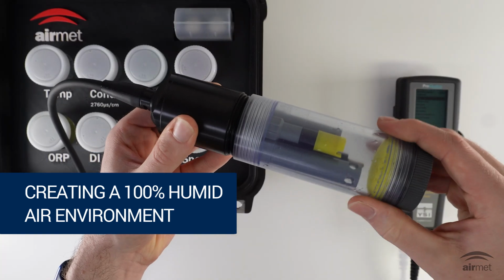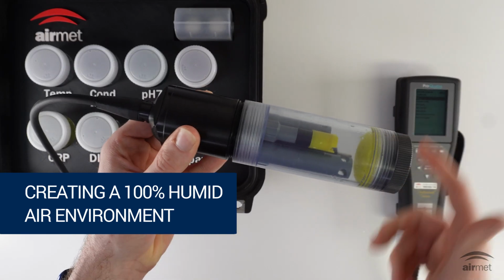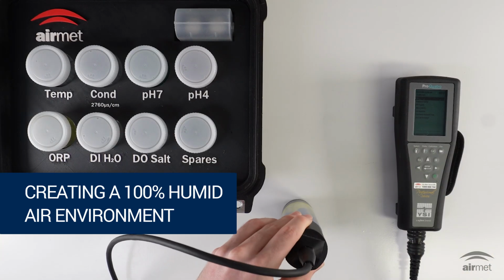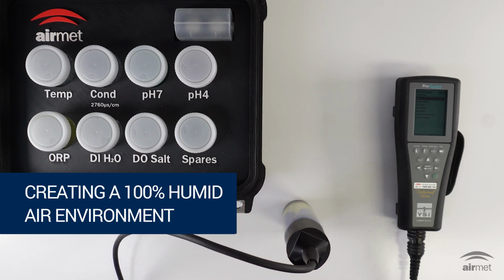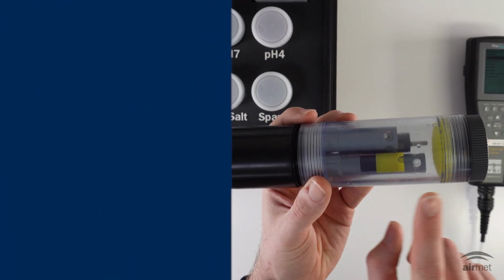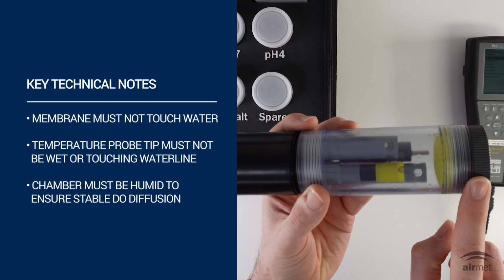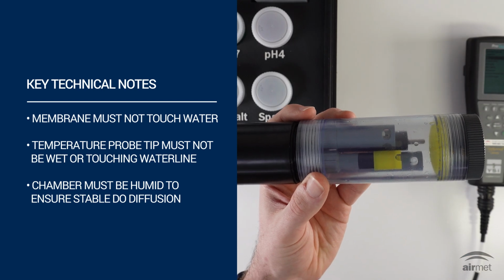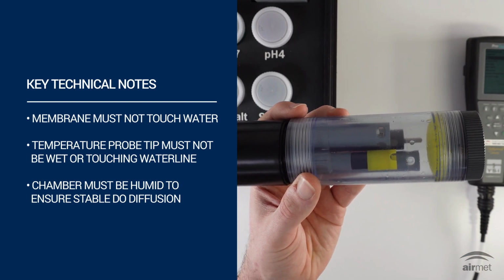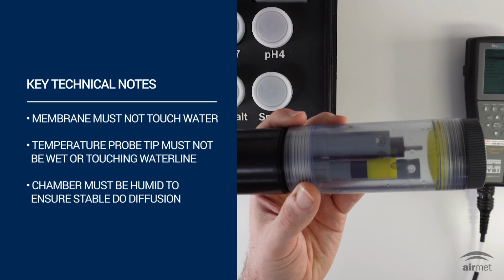Thread the calibration cup onto the probe bulkhead loosely, around 1 to 2 turns to allow pressure equalization with the atmosphere. Allow the sensor to sit in the humid air chamber for 5 to 15 minutes to equilibrate to 100% humidity and temperature. The membrane and the temperature sensor must not touch the sponge inside the calibration cup or the water line. The chamber must be humid to ensure stable DO diffusion.